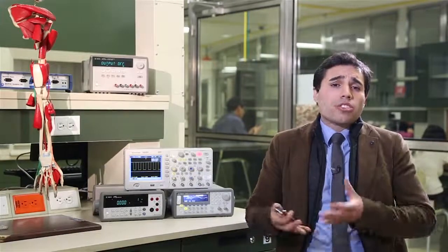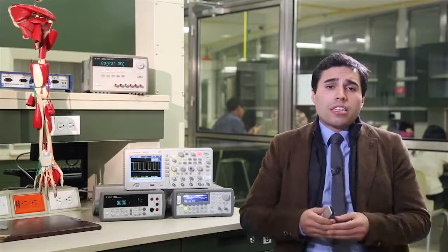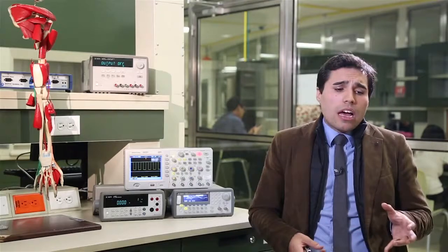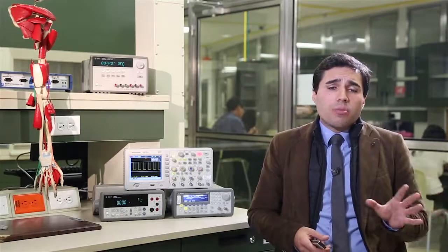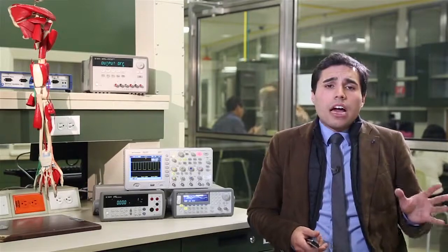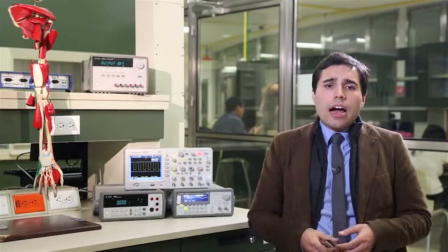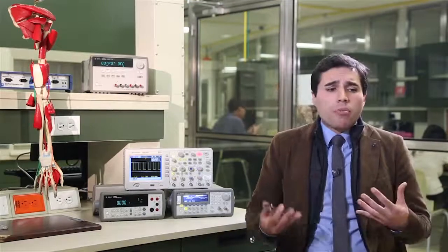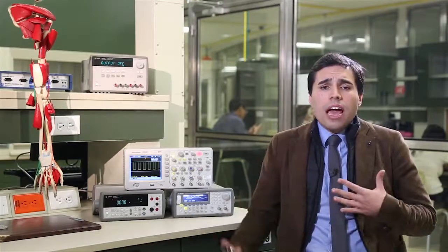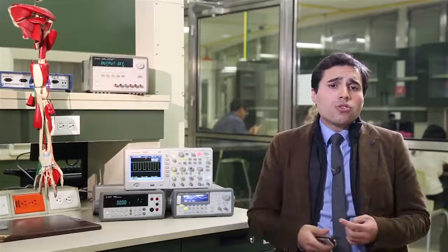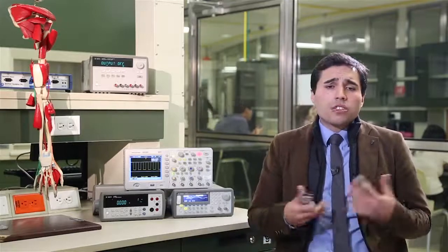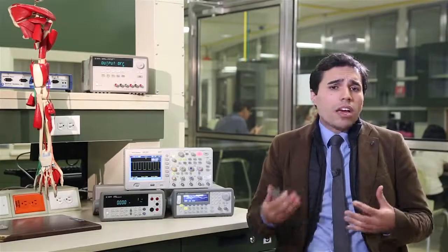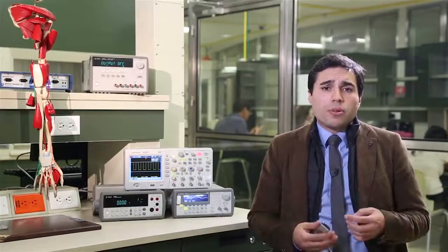But coming back to a scoring system, to the Pugh method, what you can see is that the scoring system might look just like the thing that I'm showing to you right now. It's basically a matrix as I'm describing, and on one side of the matrix you describe all your absolute criteria that must be met, your design requirements, and you basically put a weight on them. A good rule of thumb in the biodesign process, which has been used by Stanford and by JHU CBID, is to assign a weight that ranges from 1 to 3 or 1 to 5 in terms of the importance, so the larger the weight, the more important the characteristic is to be met.